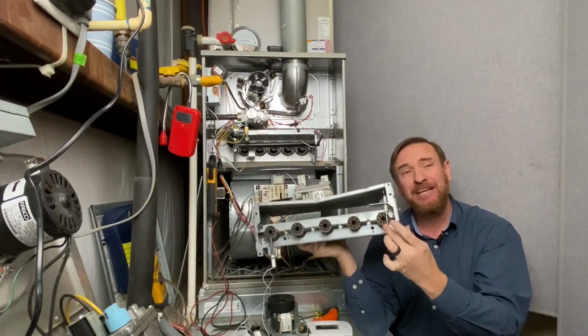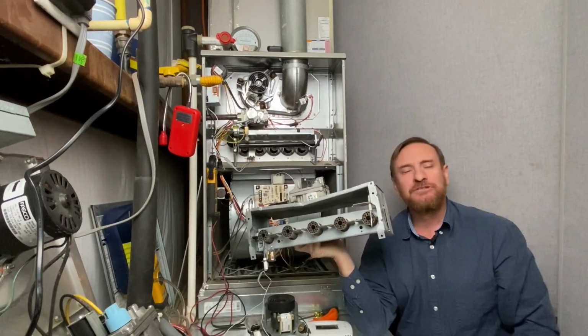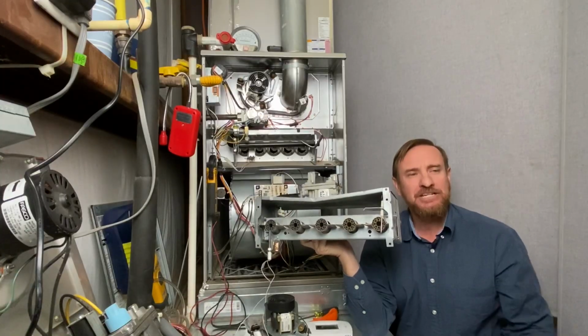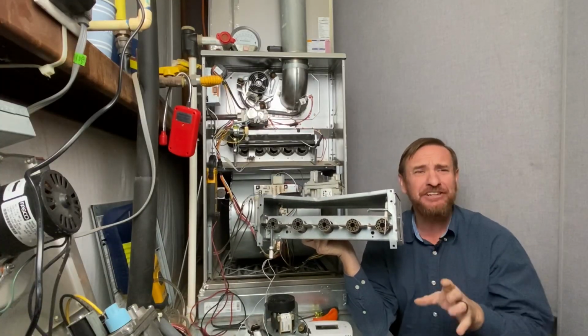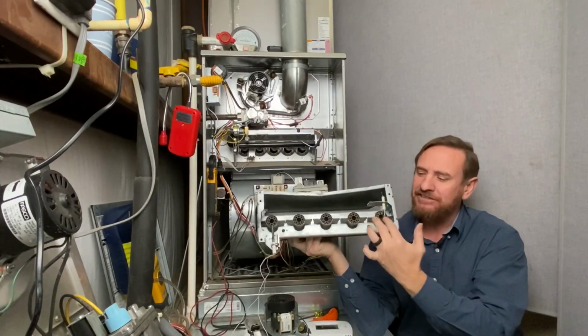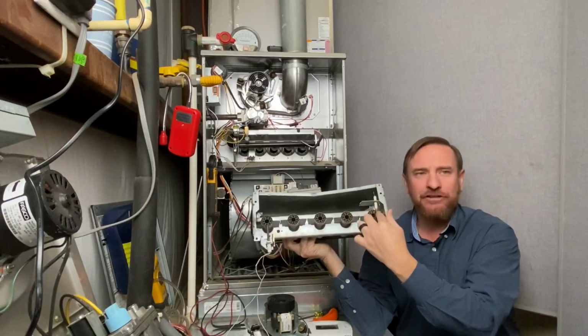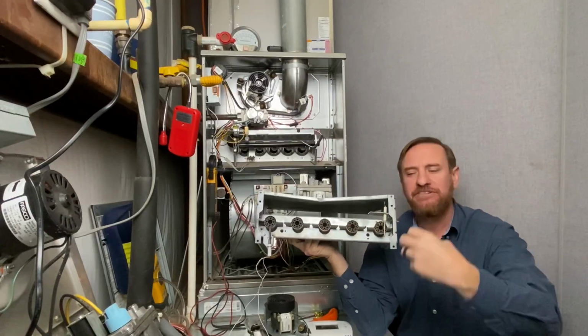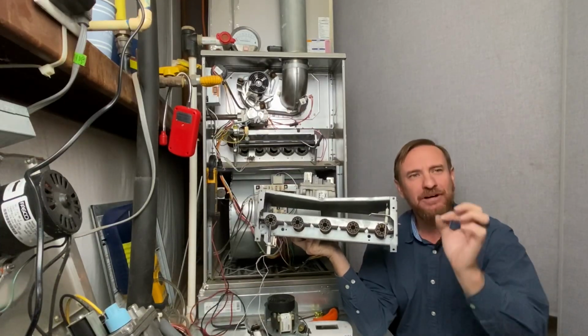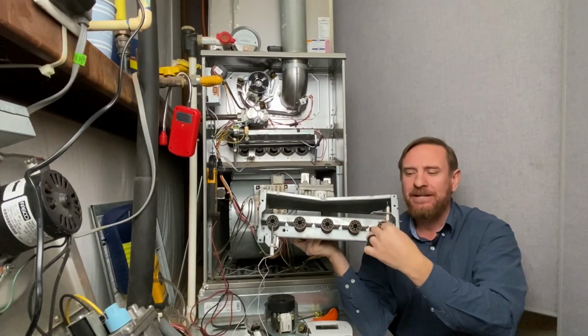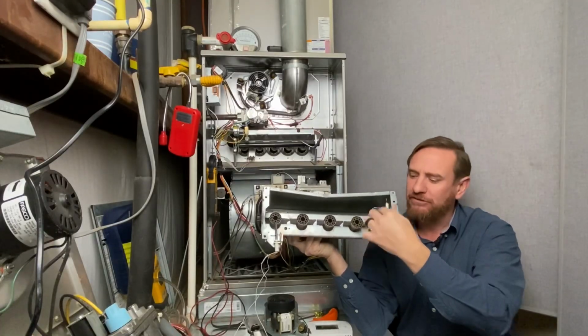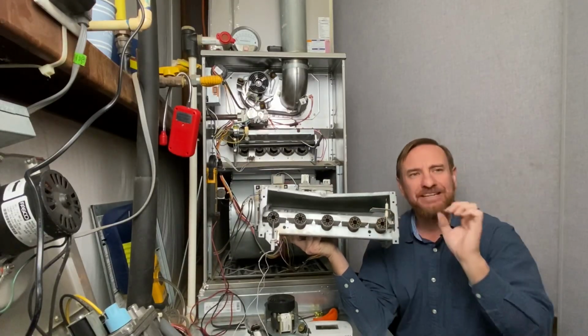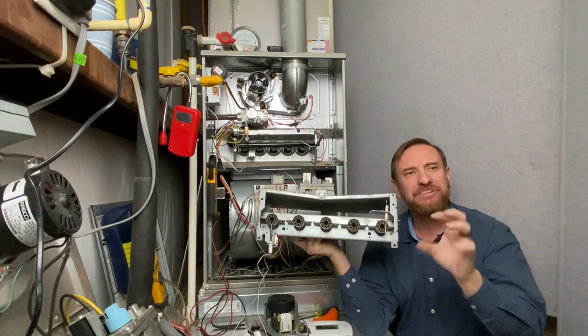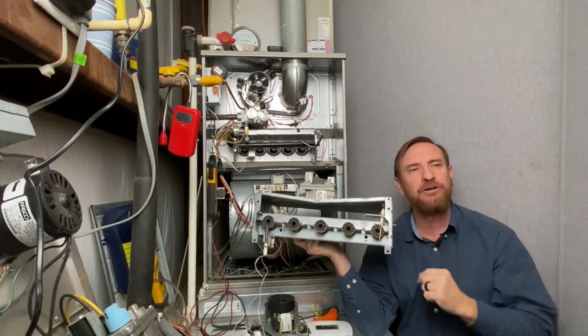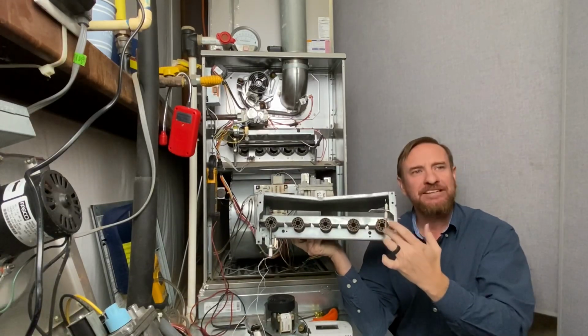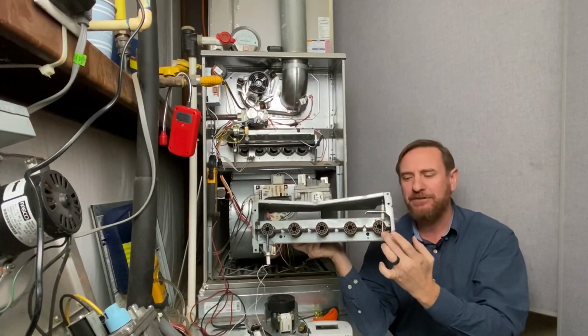And notice it said flame sensor, not a heat sensor. It uses a process called flame rectification. I'm going to do a separate video just on flame rectification, but it actually takes the AC current from this rod, and the flame conducts electricity to a very small, a micro DC amps, but it's microamps is what it's measuring. So it converts it from an AC to a DC current, a pulsating DC current that this control board is reading. So it only has a few seconds. It gives it a few seconds to prove a flame through that process.